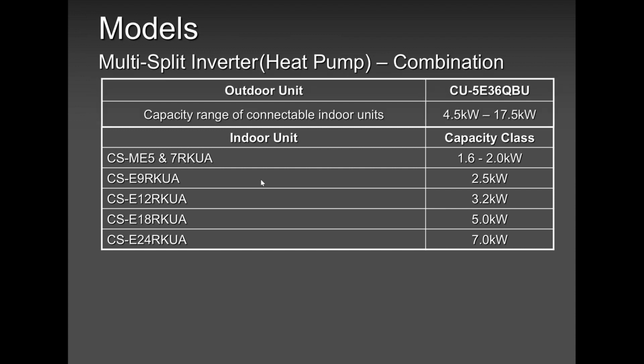But there's one thing you have to keep in mind, and that is the minimum and the maximum capacity. If you fail to maintain that, you are in trouble. And what trouble? You will get an H12 error. H12 means capacity error. You have either exceeded the maximum or you are below the minimum. So please keep in mind, guys, if you are not following this very easily, always give us a call. We will guide you in the right direction as far as the capacities are concerned. We are not here to tell you what units to put in what room. That is up to you. But we will guide you to give you what is needed to maintain this system to work well.